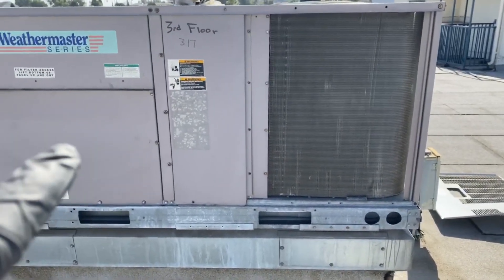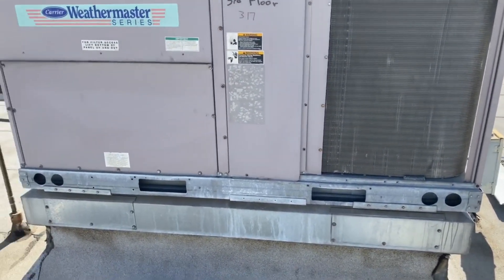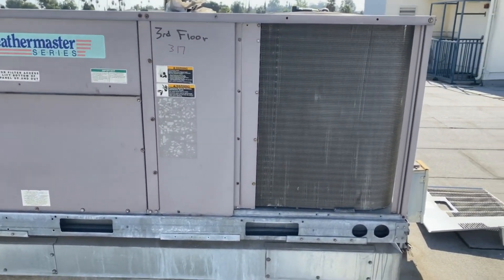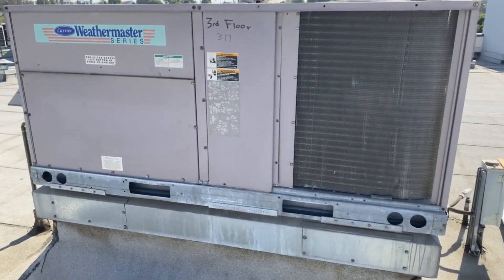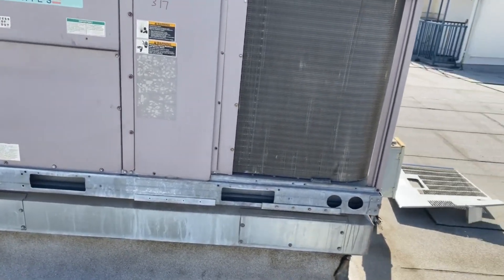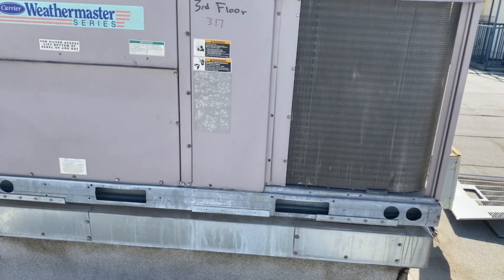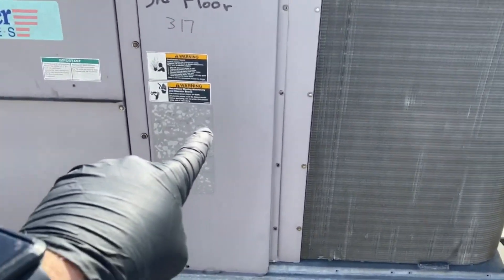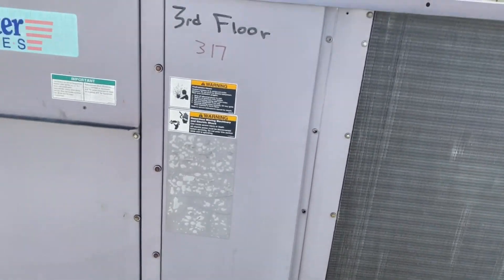The complaint is it stopped cooling and wasn't blowing any air on one of our random heat days. Now it's working sort of — I've got about a 10-degree delta between supply and return, so I came up here. I already got the job leak probes in there.